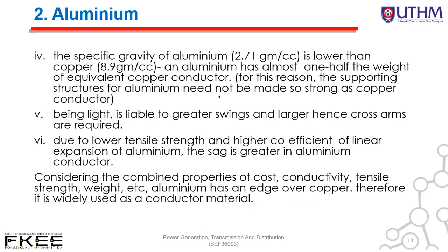The specific gravity of aluminium is 2.71 gram per cc, lower than copper, which is 8.9 gram per cc. Aluminum has almost 1/2 the weight of equivalent copper conductor. Weight is less compared to copper. For this reason, the supporting structure for aluminum need not be made as strong as for copper conductor. Because aluminum is light, it is liable to greater swing, and hence larger cross arms are required.